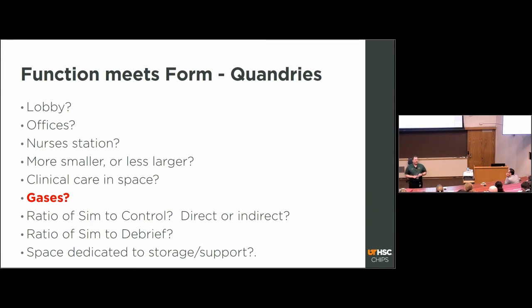That's great. The oxygen outlets on the second floor deliver real oxygen from a Dewar tank that's in our loading dock. The oxygen outlets on the first and third floor are dummies, and they deliver compressed air. And the reason we took that approach was because, first of all, the compressed air was relatively free. And if we were using oxygen, say, on standardized patients on the third floor, we wouldn't really want to administer real oxygen in those situations.